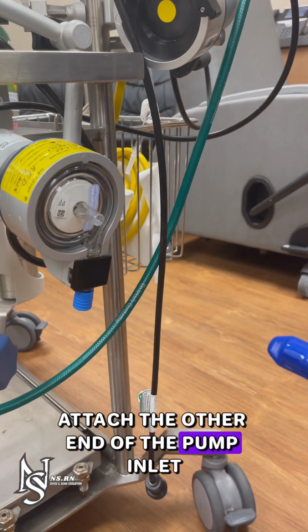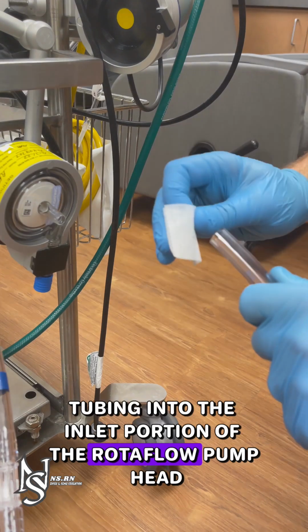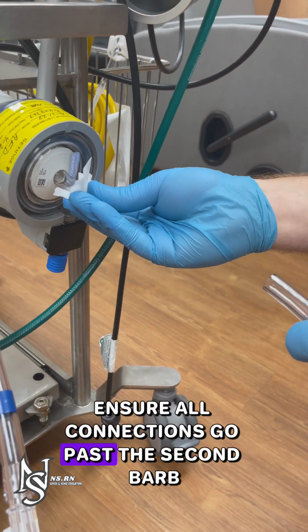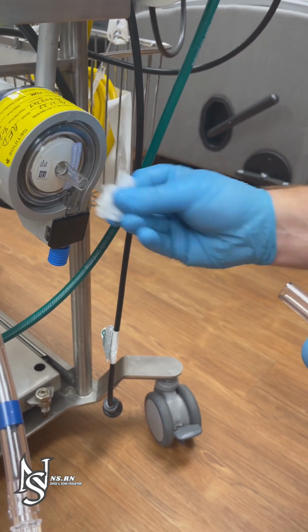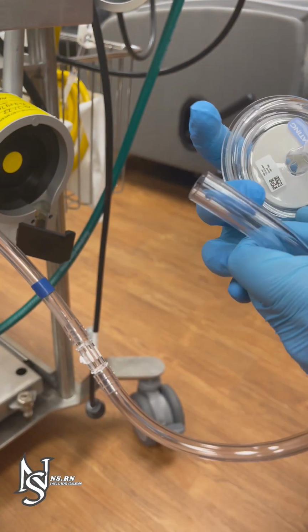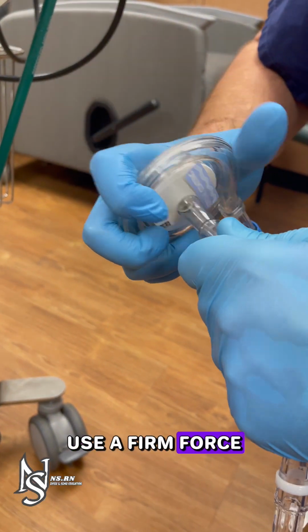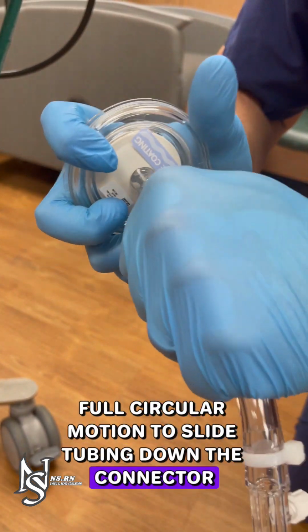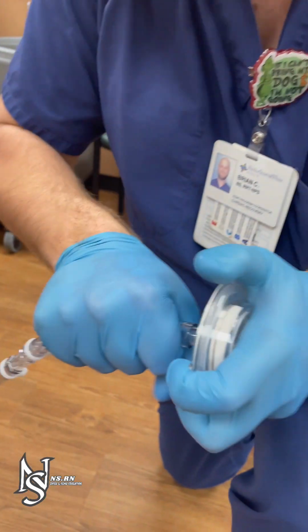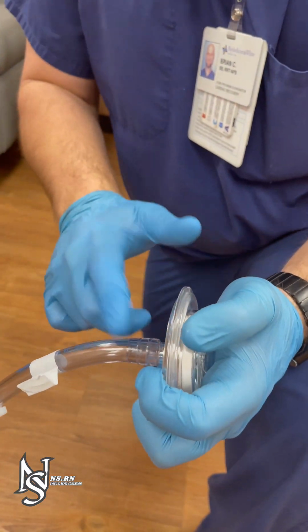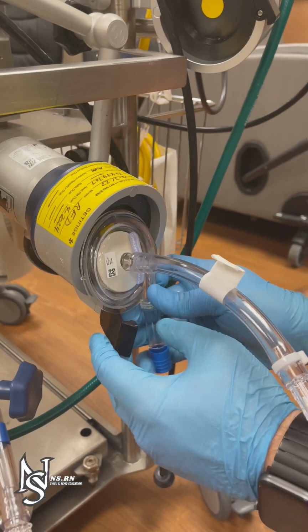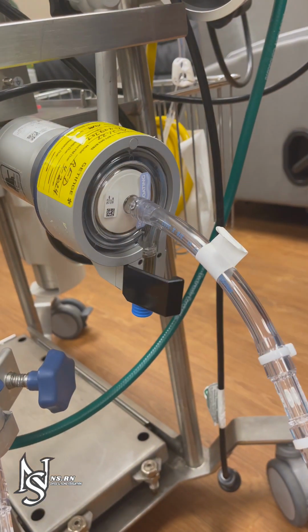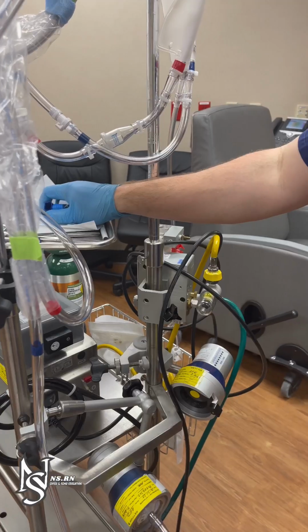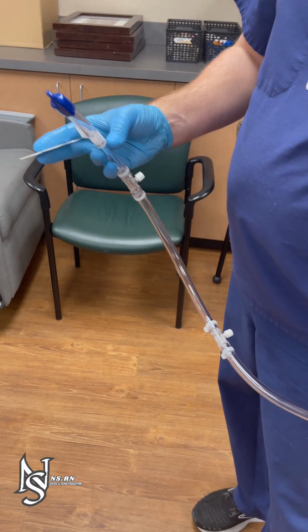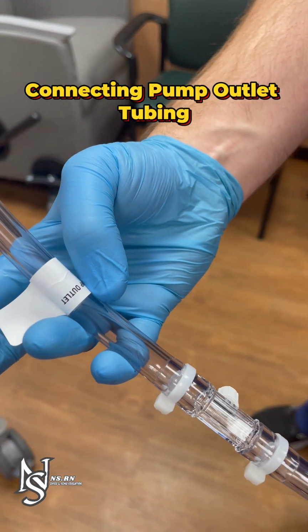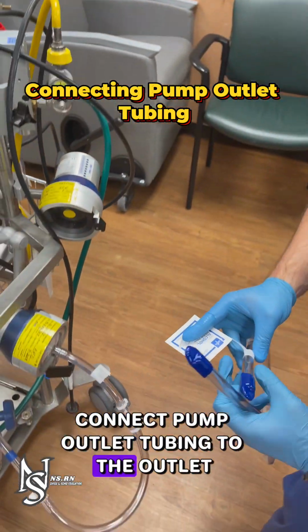Attach the other end of the pump inlet tubing into the inlet portion of the Rotaflow pump head. Ensure all connections go past the second barb. Use a firm, forceful circular motion to slide tubing down the connector. Connect pump outlet tubing to the outlet end of the pump head.